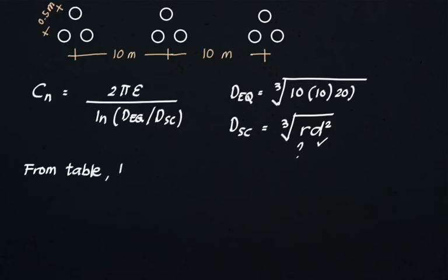Again, from the table. So, the Finch conductor as described here, the ACSR, and then you locate 1,113 kcmil. There might be a table there where there are two entries for 1113. If ever, there is a table that is very particular, specific only to Finch, the 1,113 kcmil.